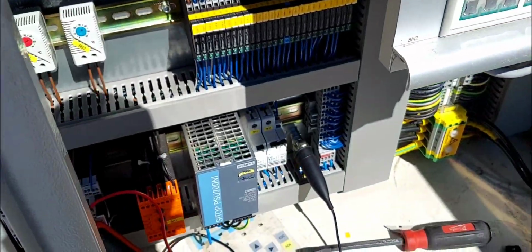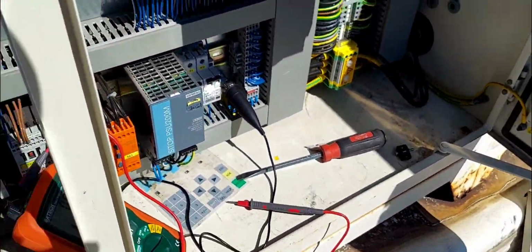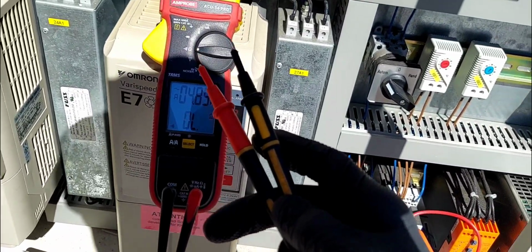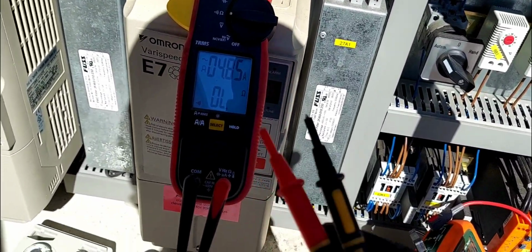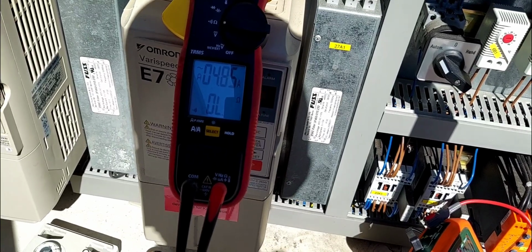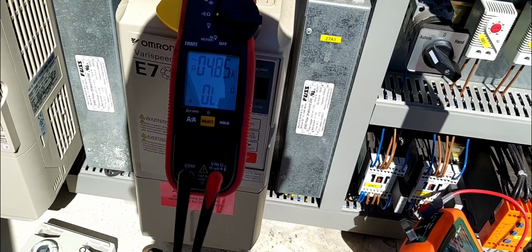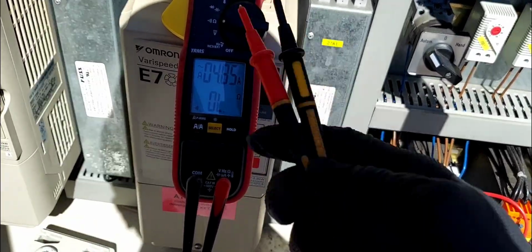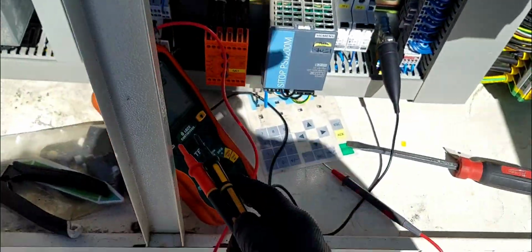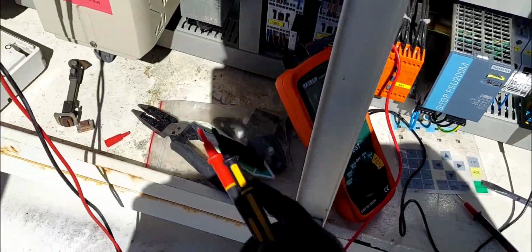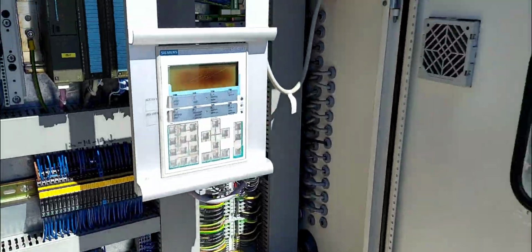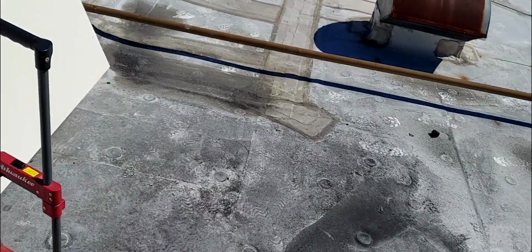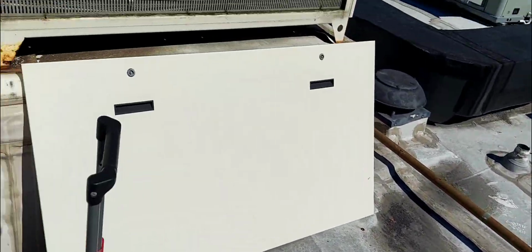It passed my Meg tester at high voltage, 1000 volts, while this meter uses only two AA batteries, so that's only, what's that, 3 volts, 6, 7, wait a minute, 3.5, yeah, 7 volts. That's all this puts out. This puts out a whopping 1000 volts. All right. So I think, guys, that's it for this video regarding compressor or motor windings Megger testing.